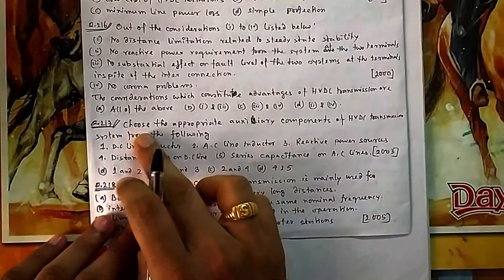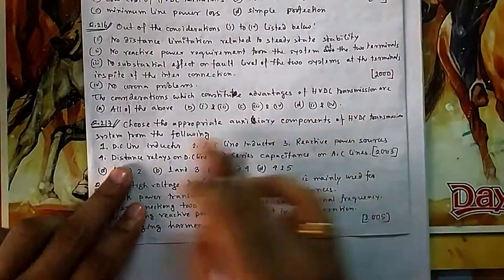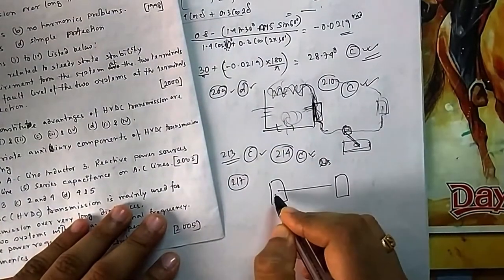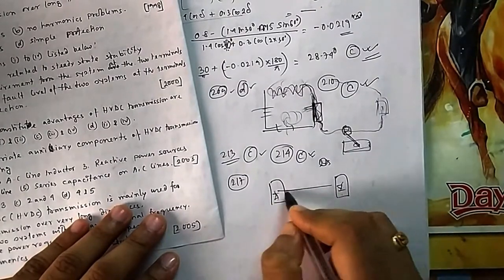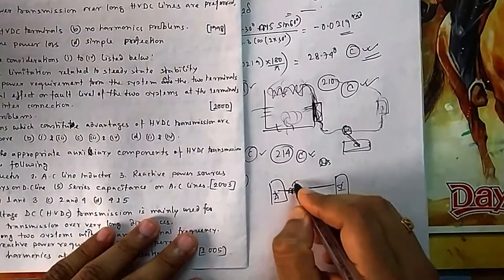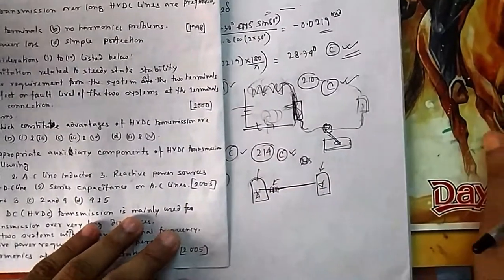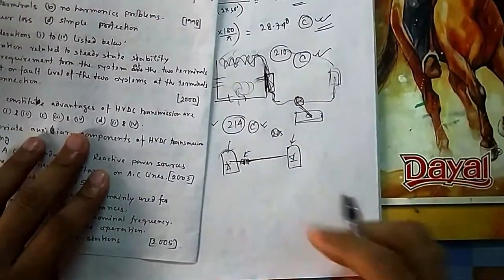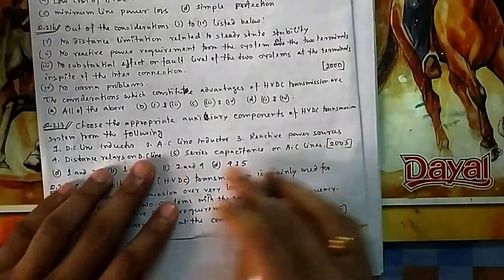Question 217: choose the appropriate auxiliary components of an HVDC transmission line. A DC inductor — yes, in an HVDC link we provide an inductor in series. This DC series inductor is provided to reduce harmonics in the line. Because of the rectifier and inverter there will be harmonics in the current, and the inductor doesn't allow sudden changes in current, thereby reducing harmonic content.